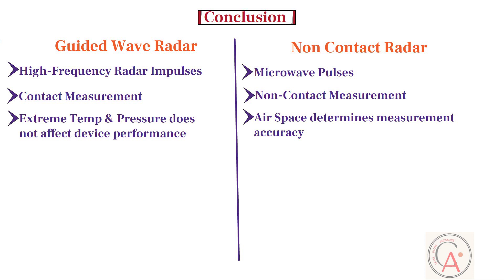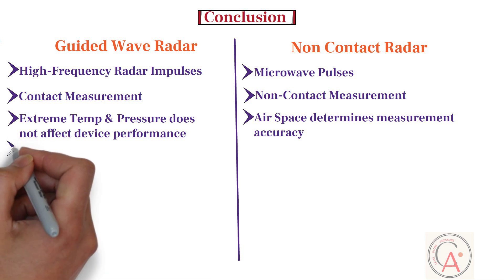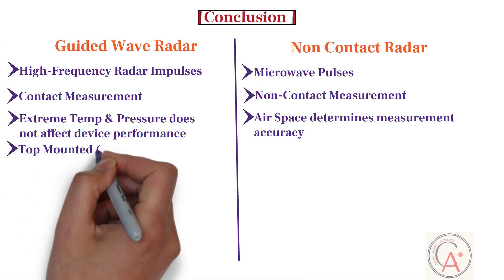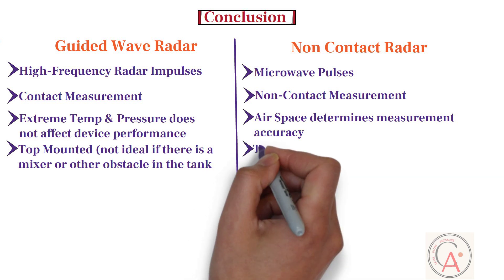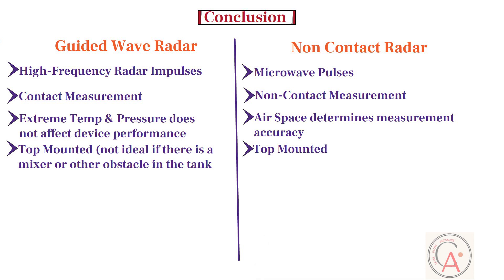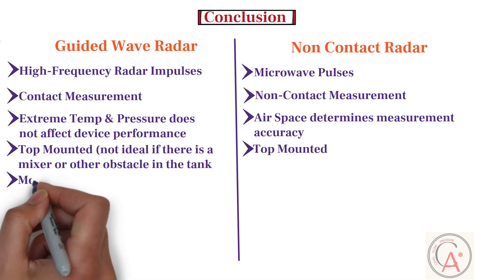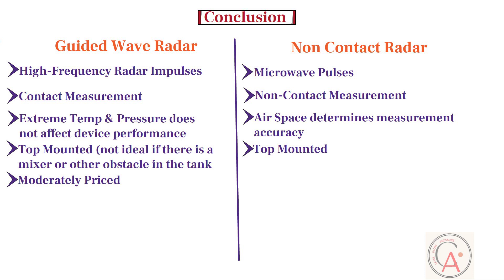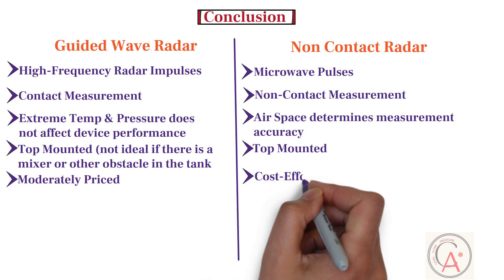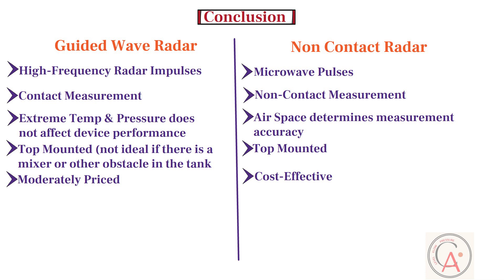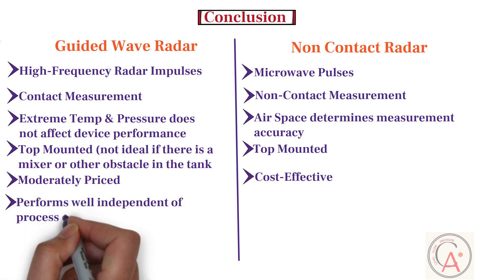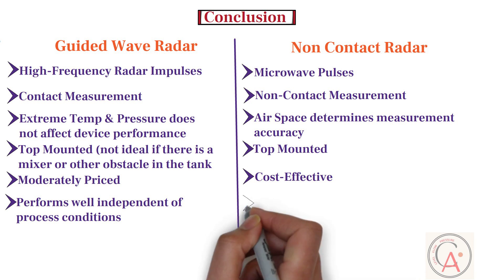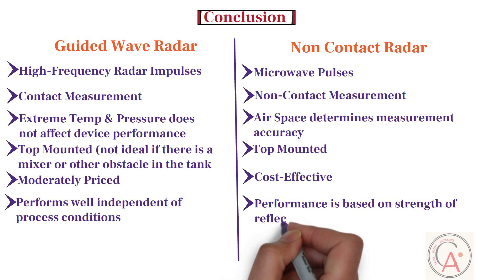Fourthly, guided wave radar is mounted on the top of the tank and is not ideal if there is a mixer or other obstacles inside — and pulse radar shares the same limitation. On the price perspective, guided wave radar is moderately priced, whereas pulse radar is very cost-effective. Finally, in terms of performance, guided wave radar is exceptional and performs well independent of process conditions, while pulse radar technology's performance depends on the strength of reflections and surface conditions.